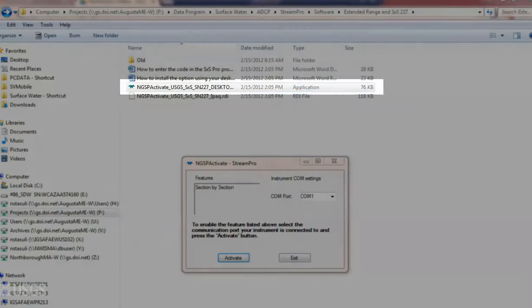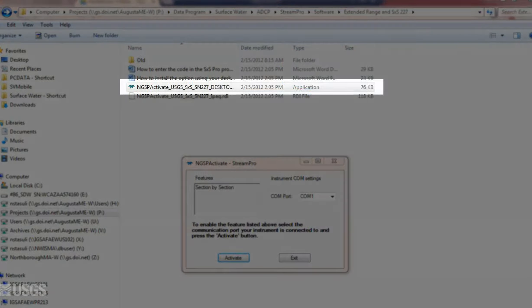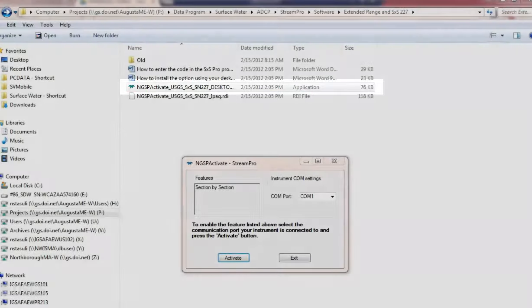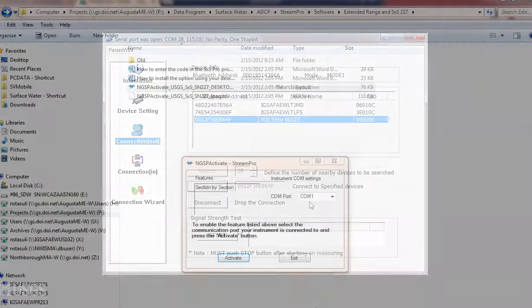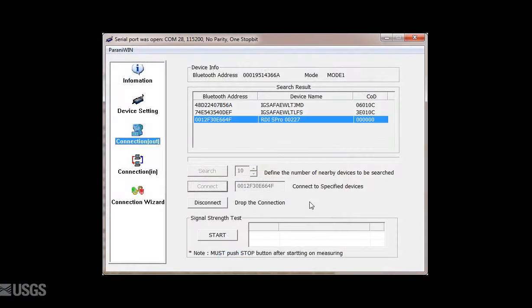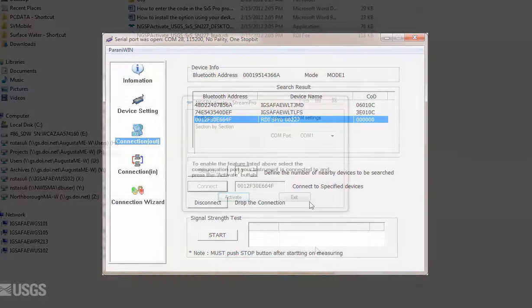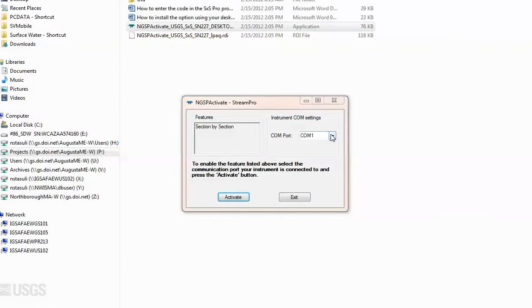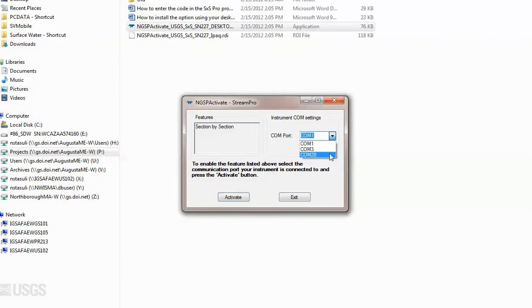Once you've purchased the license, you first enable the unit by running the executable file you received. This sets the unit's firmware to allow data collection. This is a simple process. First, connect to the ADCP, whether it be through a Bluetooth connection or a direct connection. Once you open the executable, simply specify the COM port you used to connect to the ADCP and click Activate.